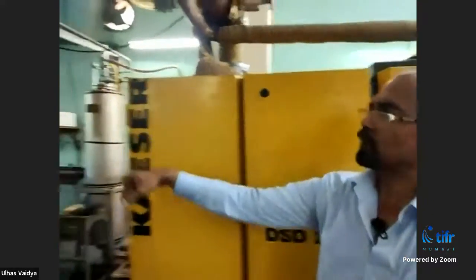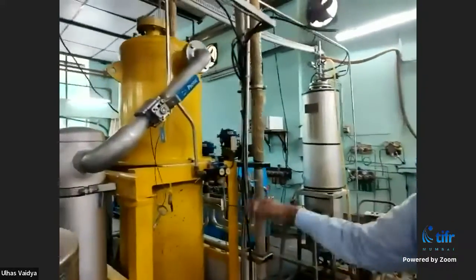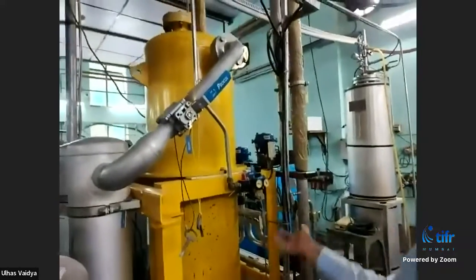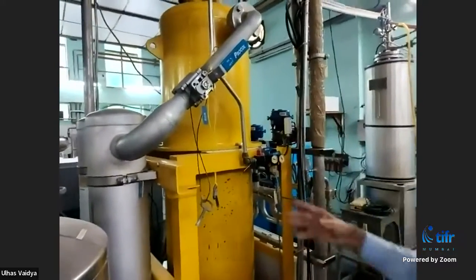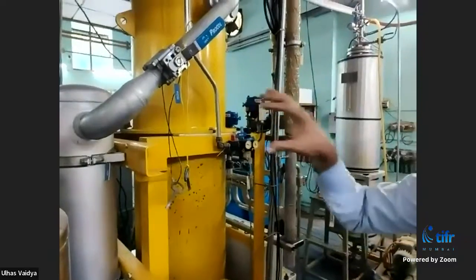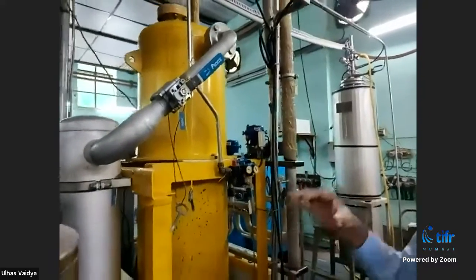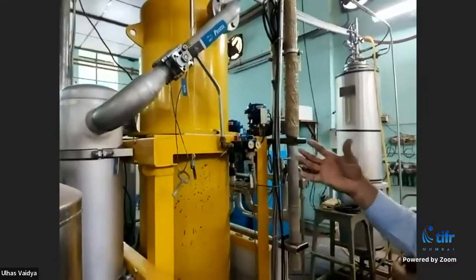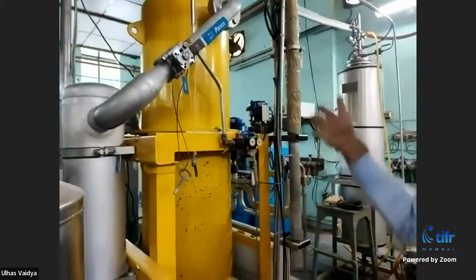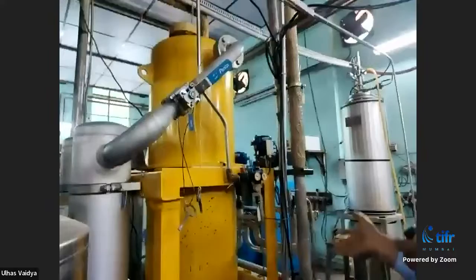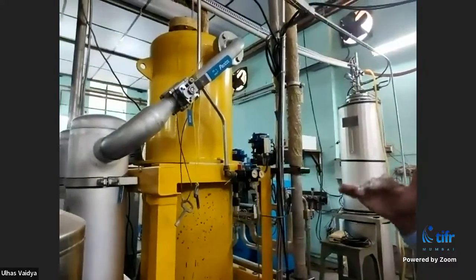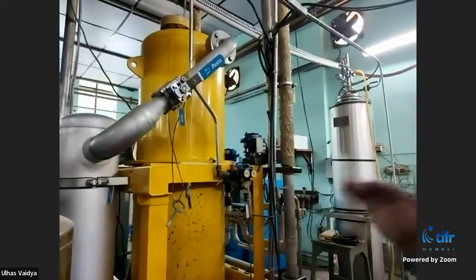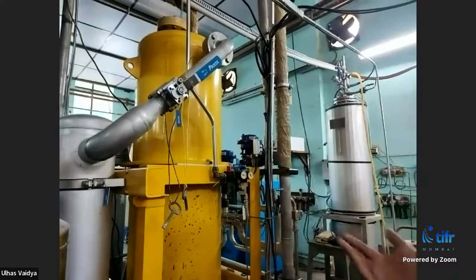Then it goes to the gas management panel, where moisture and oil traces are removed from the gas, and it delivers controlled pressure and controlled flow gas to the cold box. So this is basically a filter unit and control unit for maintaining pressure and flow.